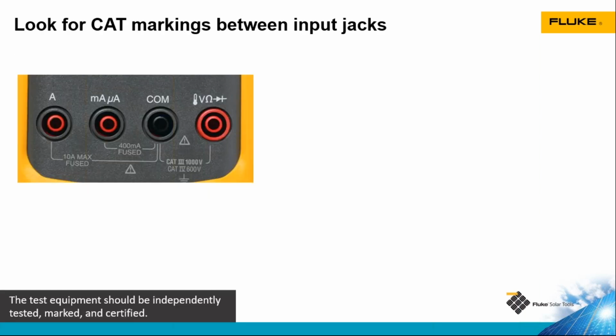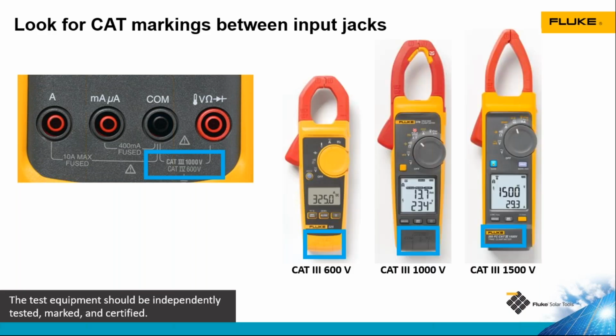Now, it should be easy to find category ratings on your tools. This is an example of a Fluke multimeter. This is category 3 1,000 volt rated, category 4 600 volt rated, printed right on the tool itself. It is very common to see a higher category 3 voltage than category 4 voltage because the intensity of those transient voltage spikes is greater in a category 4 environment.